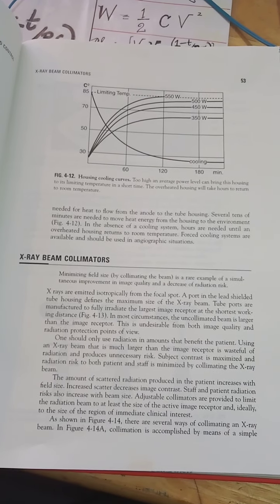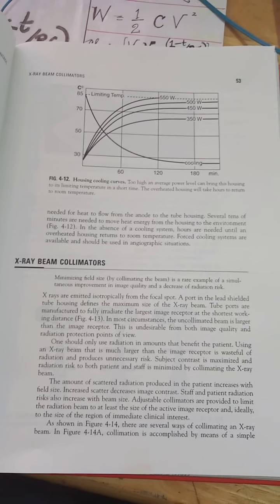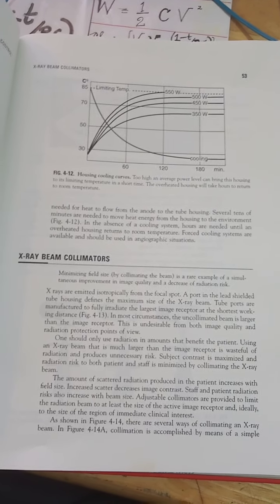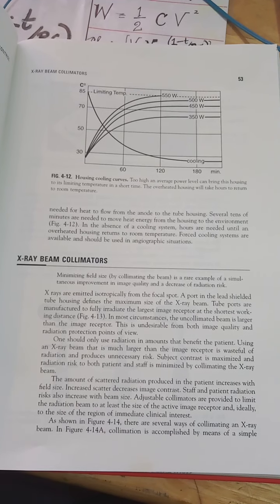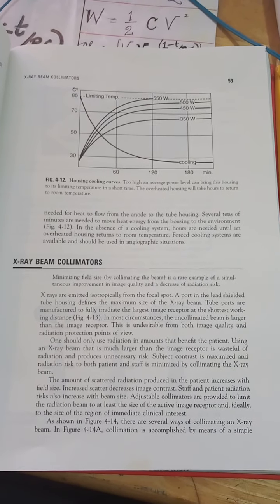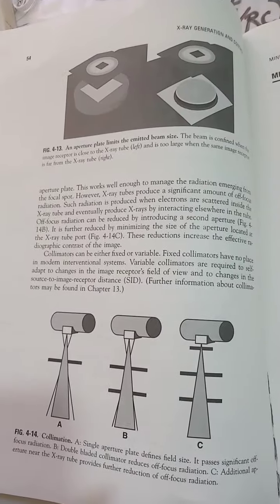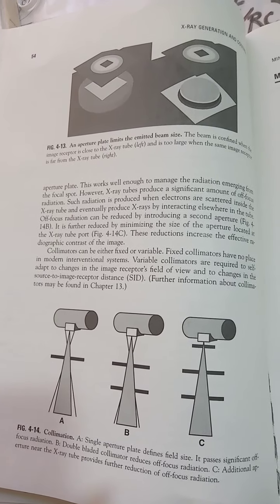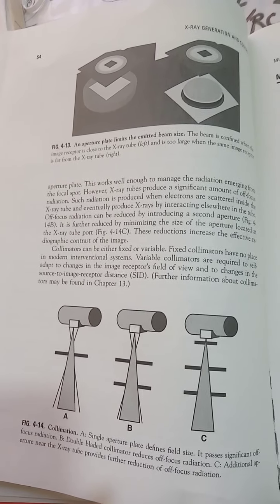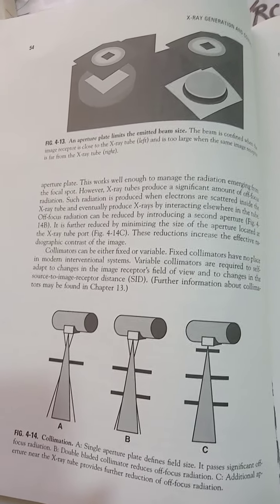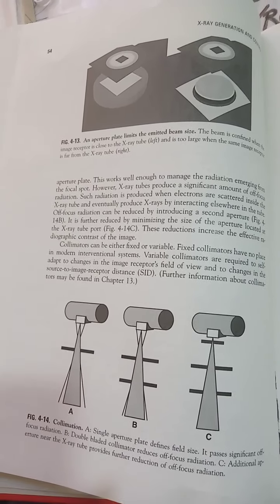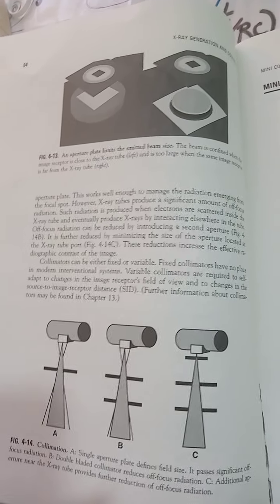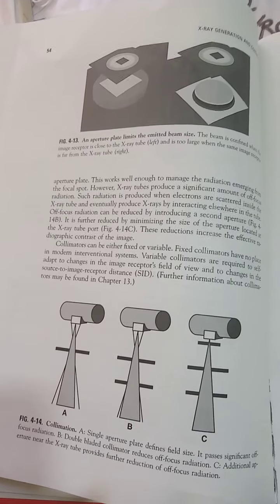Adjustable collimators are provided to limit the radiation beam to at least the size of the active image receptor and ideally to the size of the region of immediate clinical interest. So that's what the diagrams are talking about. And the aperture, plate limit, and the emitted beam size for the square focal spot is shown here. I know this is slightly complex, but you have to read through it to be able to understand, and you have to make notes and mathematical symbolic notes as you go along the chapter.